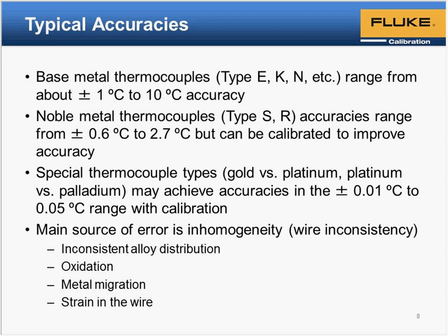So, just some basic accuracies. There are general categories of thermocouples. Base metal thermocouples like type E or type K are made out of non-noble metals, things like nickel or copper or iron, and they have a little harder time holding consistency over time. So their typical accuracies are 1 to 10 degrees. When you consider that some thermocouples go up well over 1,000 degrees Celsius, that's where you're seeing 10-degree accuracies. Noble metal thermocouples like type S and type R have better accuracies, and they are stable enough that they can also be calibrated to help improve accuracy a little bit. The accuracies we have here are the off-the-shelf accuracies, like the ASTM special limits of error accuracy, for example.